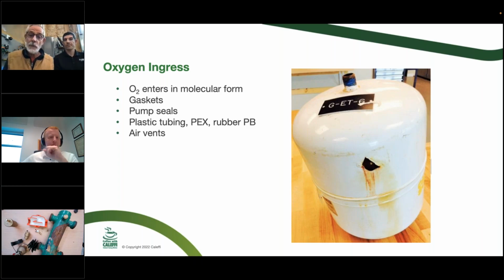Now, there's a couple ways you can deal with that. You could put an oxygen scavenger chemical in there that would take any oxygen that comes in, but you got to keep doing it. You got to replenish it every year or so. Or you could separate that and put all non-ferrous components in. Put a flat plate heat exchanger on the tubing side of it. Put a non-ferrous pump in there, a stainless steel pump, a stainless steel expansion tank, and just get all the ferrous metals out of there, and then there's nothing to corrode. But it's going to keep happening if you don't.